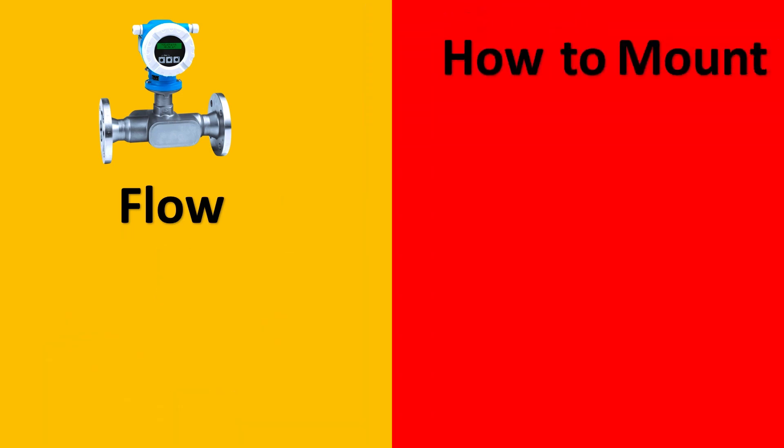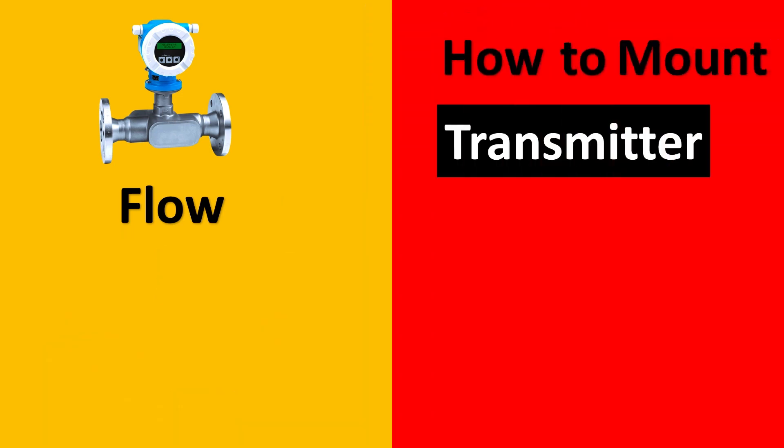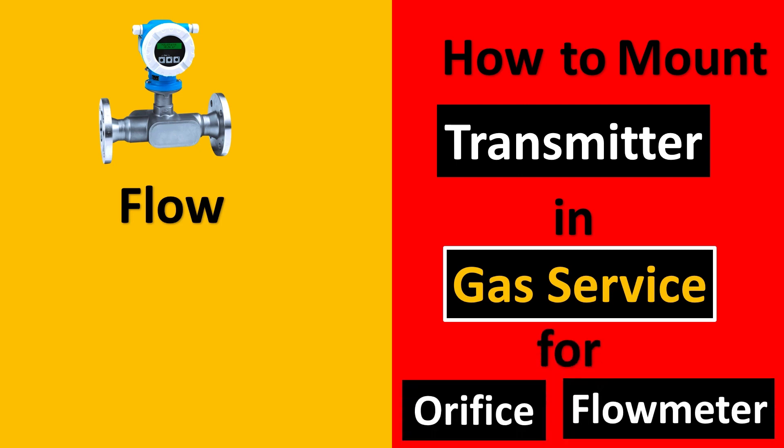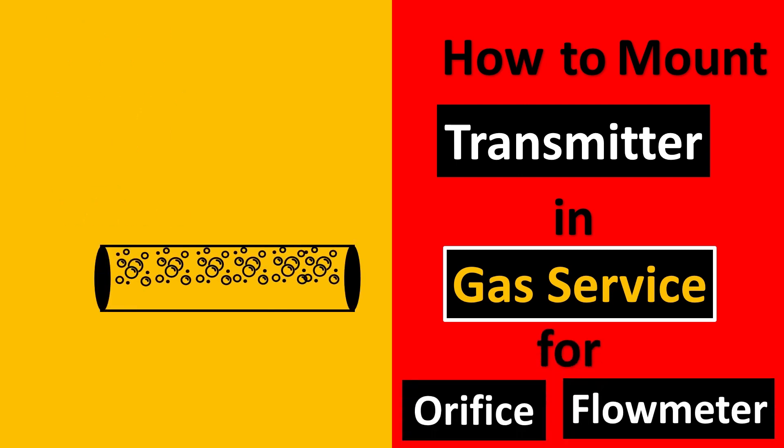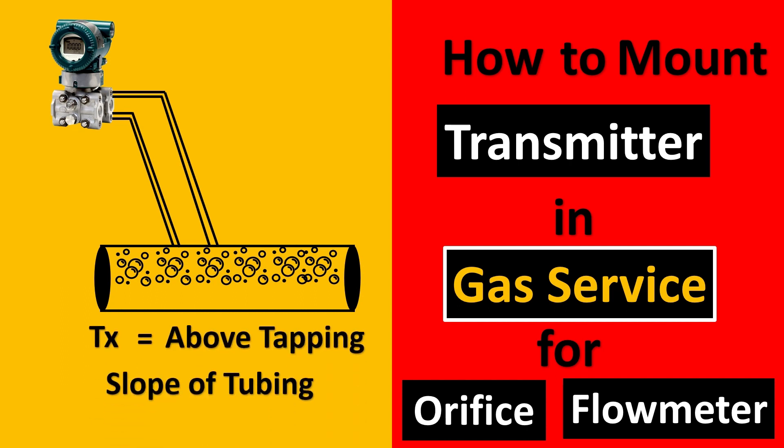In flow, one of the most asked questions is how to mount the transmitter in gas service, especially for orifice flow meters. So let's take this example. Here's your pipe and here's gas flowing through it. Now the transmitter is put on top of the pipe or top of the tapping and the second thing which is important to note here is that the slope of the tubing has to be towards the pipe.